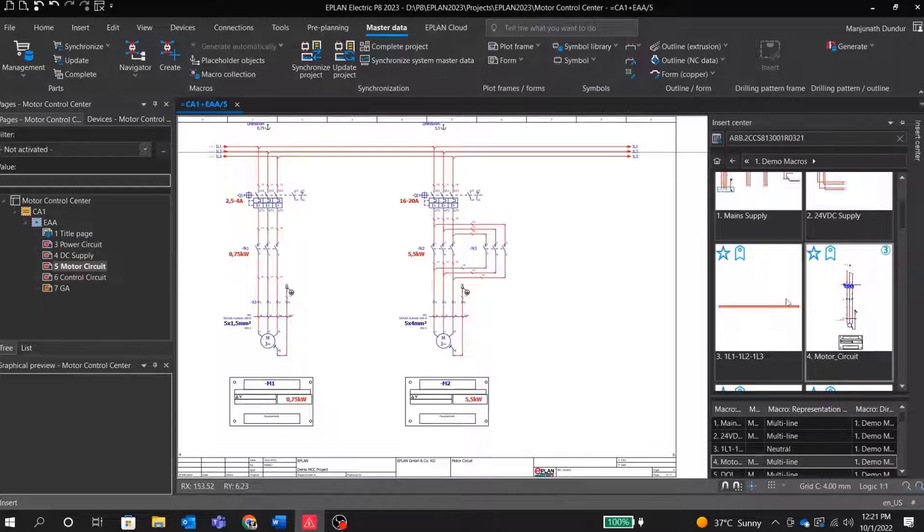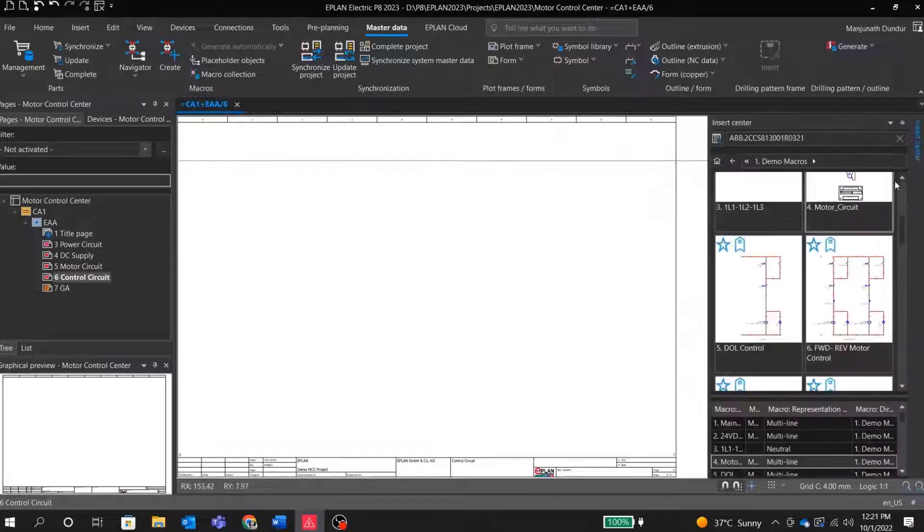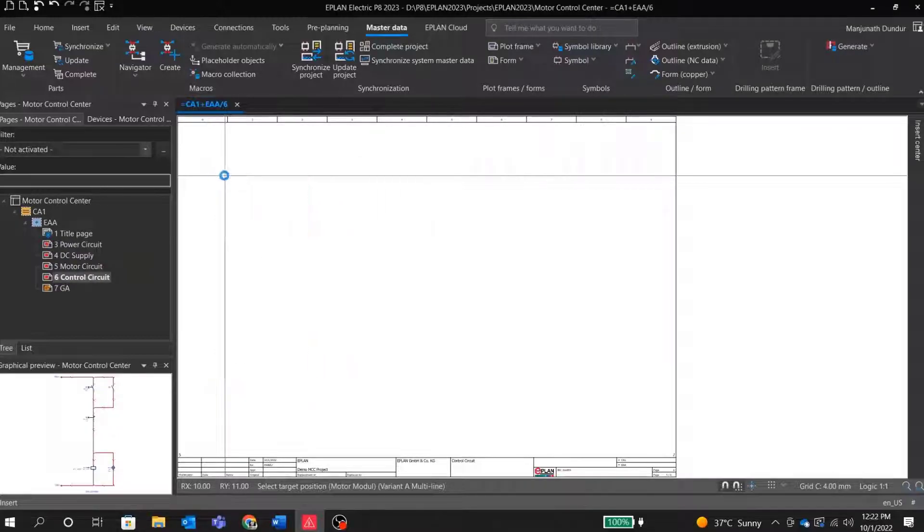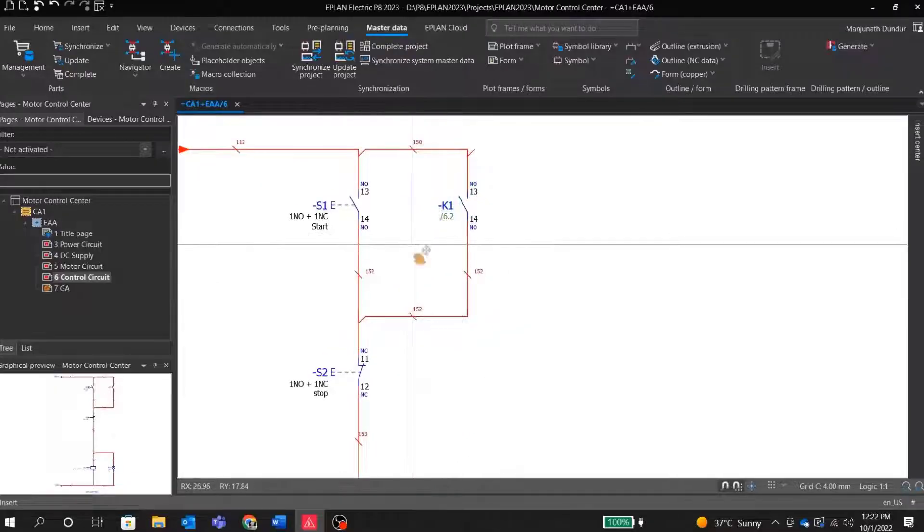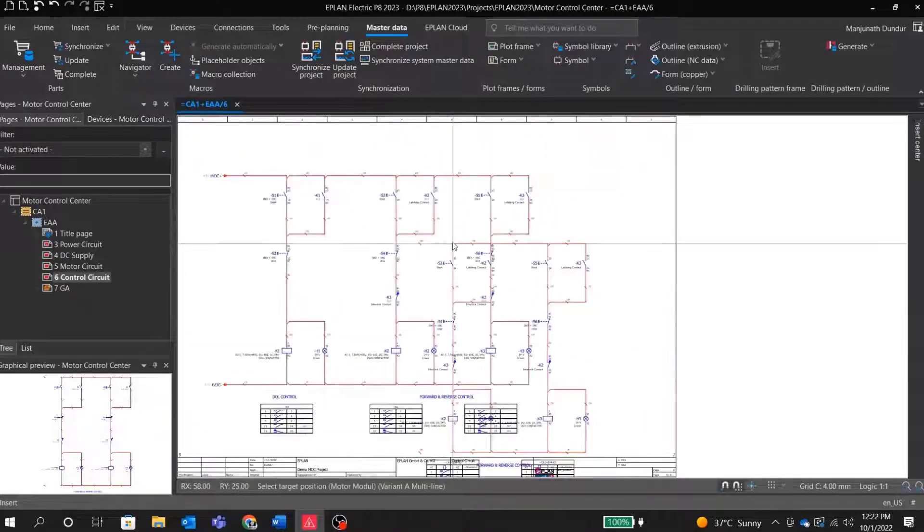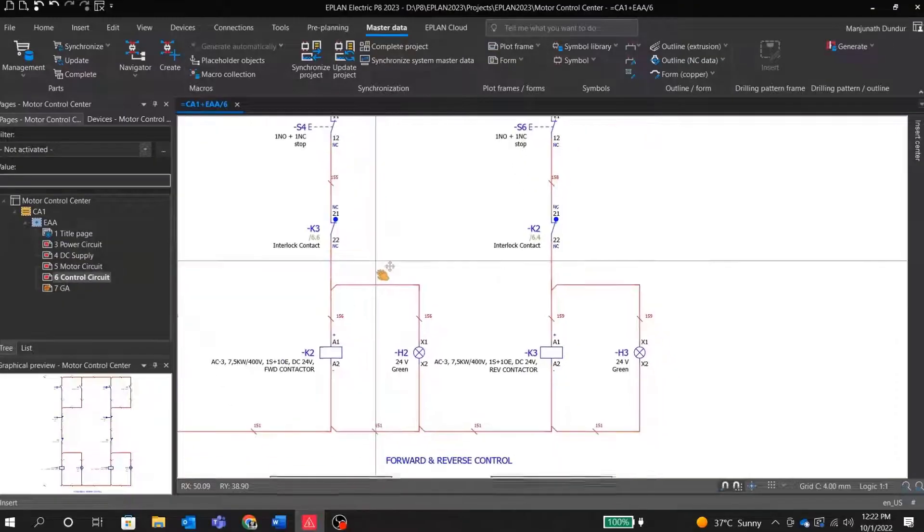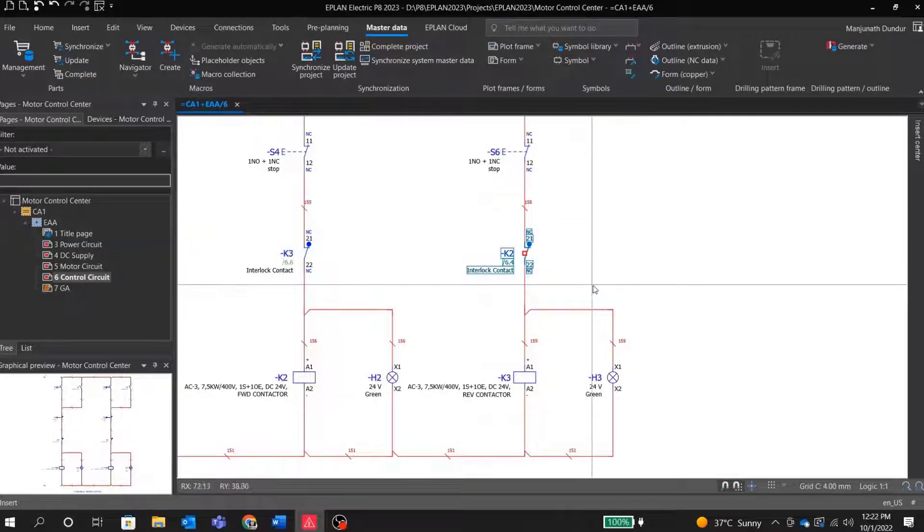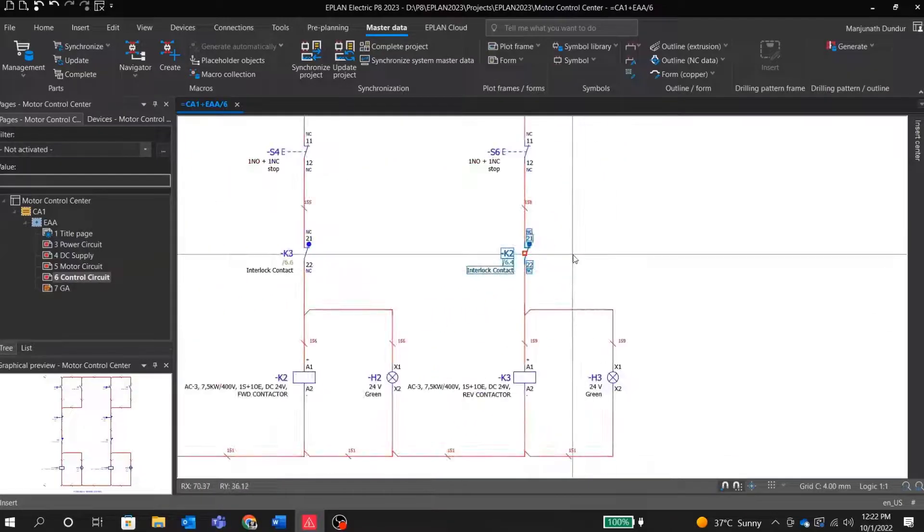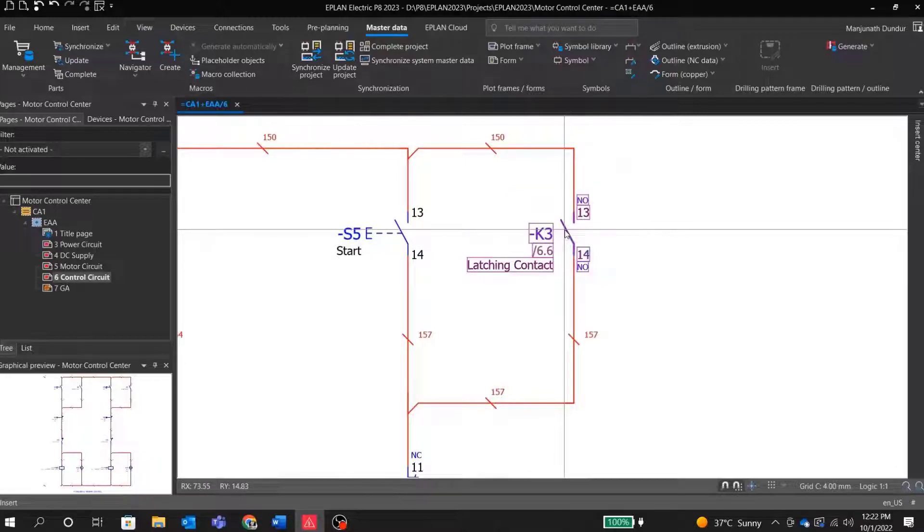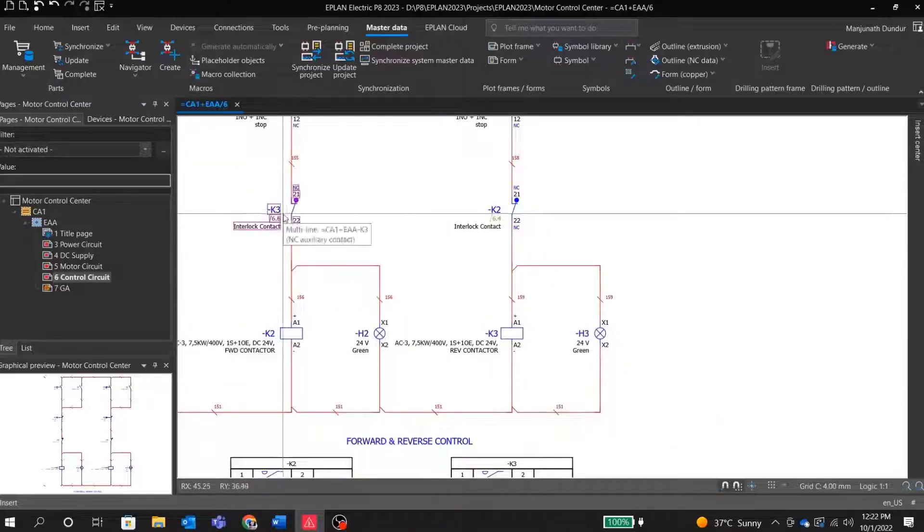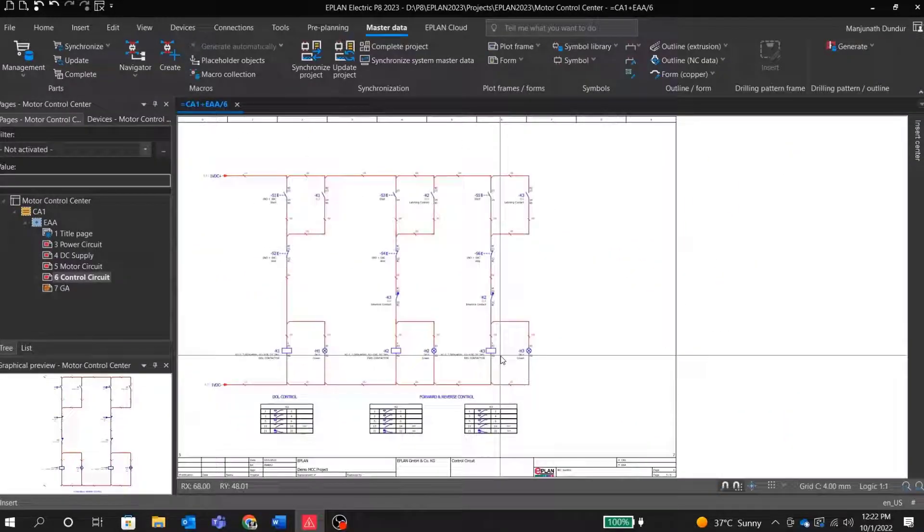Moving ahead. Now, we will create a control circuit for the DOL starter. Let me drag and drop a macro for the control circuit of the DOL starter. This is a DOL starter with contactor K1 and there is a latching here for the start push button. Now, let me bring the forward and reverse motor control circuit. Zoom it a bit. We have our forward contactor and a reverse contactor with interlocking for each contactor, to make sure if the motor is running in a forward direction, it should not be able to run in a reverse direction and vice versa. All cross-references for NO and NC are automatically updated. If you want to see any, I can simply click on that. It will take me to the contactor where it is used in the drawing. Again, from here, you can jump back to the previous control drawing by clicking here. In short, everything is interconnected.